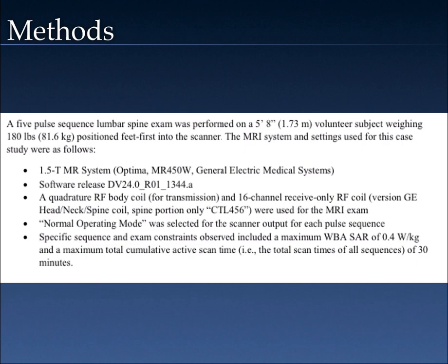The normal operating mode was selected for the scanner outputs for all of the pulse sequences — both for RF and gradient. The specific sequence and exam constraints, as previously mentioned, were a whole body SAR of 0.4 watts per kilogram and a maximum total cumulative active scanning time of 30 minutes for all sequences combined.